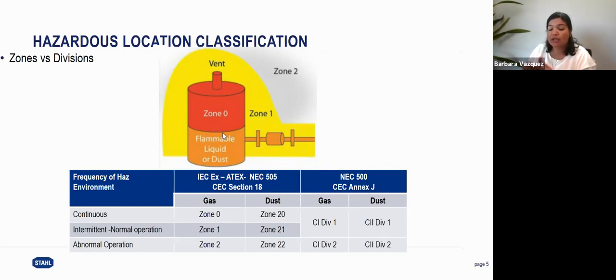Now, when we are talking about a classification as class division, here we have Class 1, which is for gas, Class 2, which is for dust, and Class 3 for fibers. Division 1, in this case, is when you normally have a presence of this explosive atmosphere. So here we can see how it takes zone 0 and zone 1. And zone 2 will be abnormal operations, not that often.